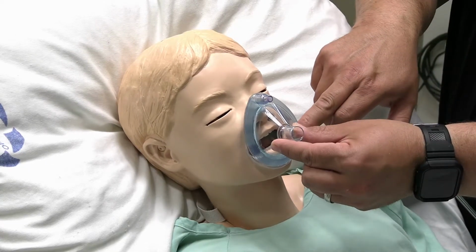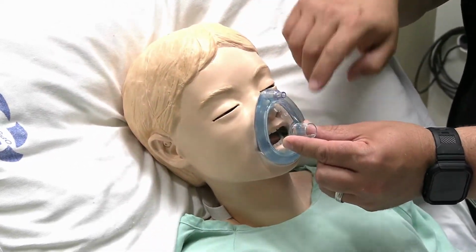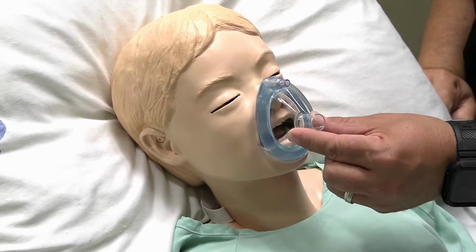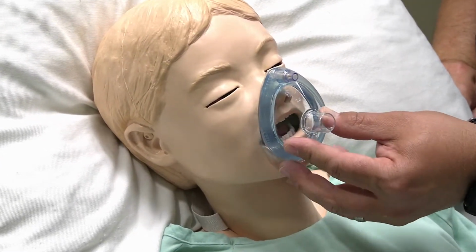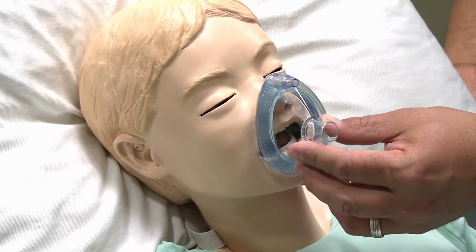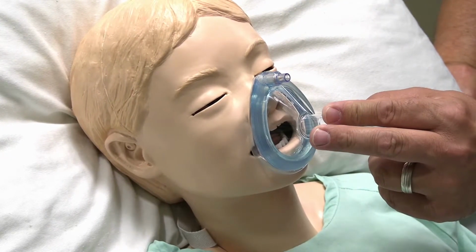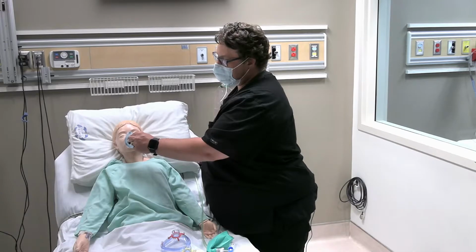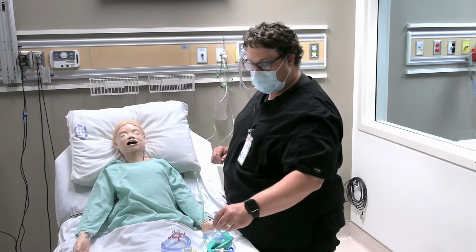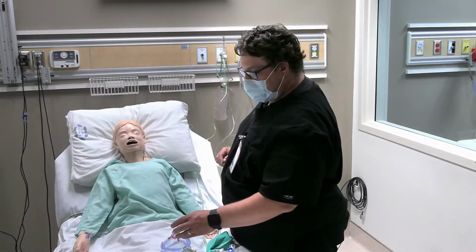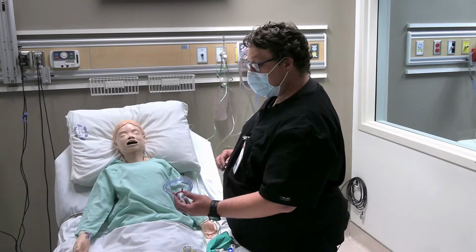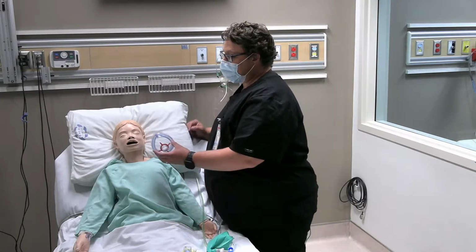It's actually got holes here at the corner of the mouth. It's not fitting nicely over the bridge of the nose, and the lip is kind of caught underneath on the bottom there. You can barely see that, but that's a good indication that this mask is too small for this patient.